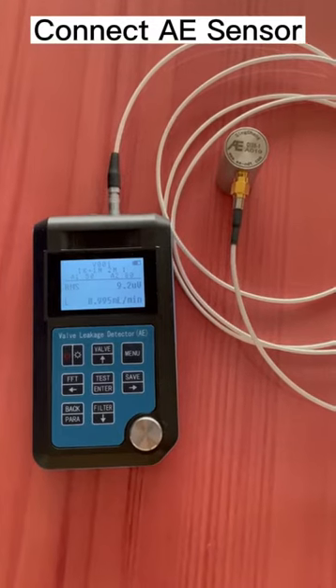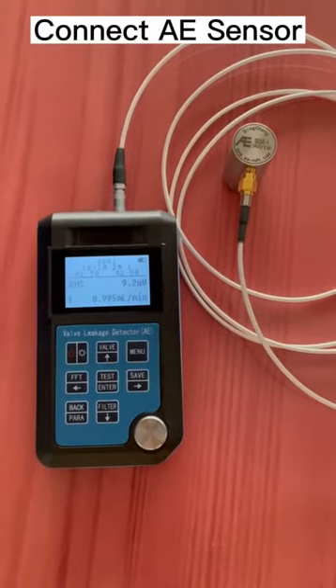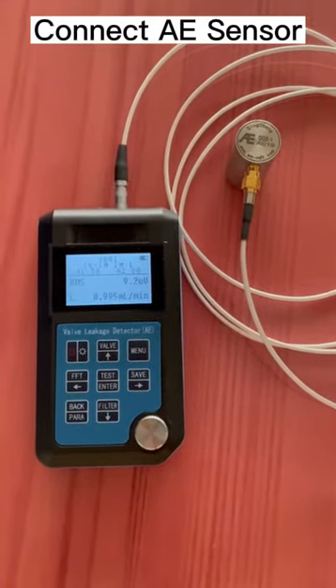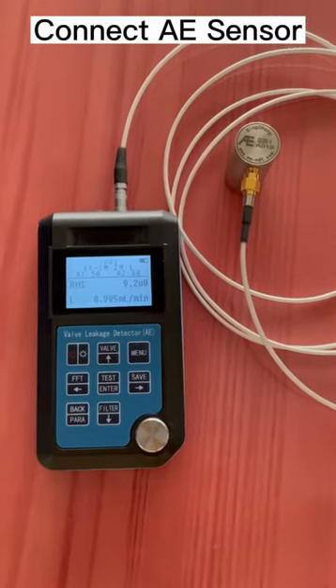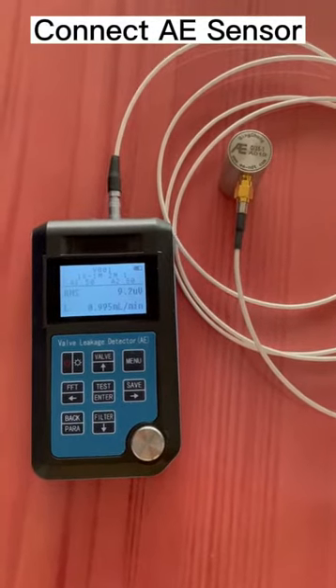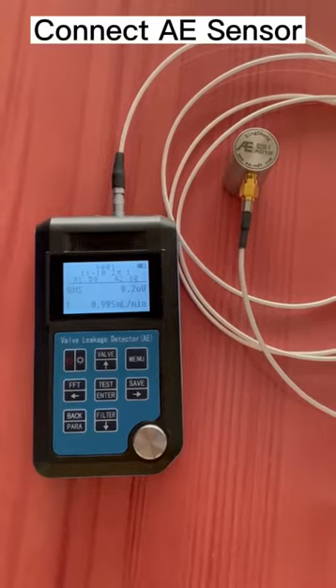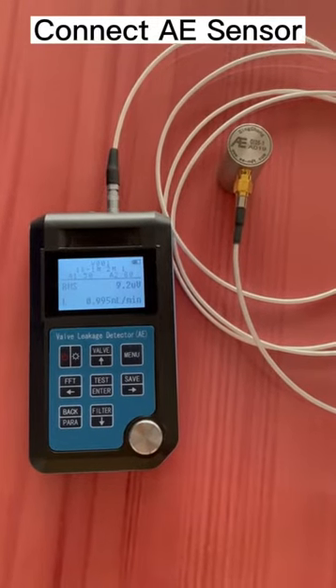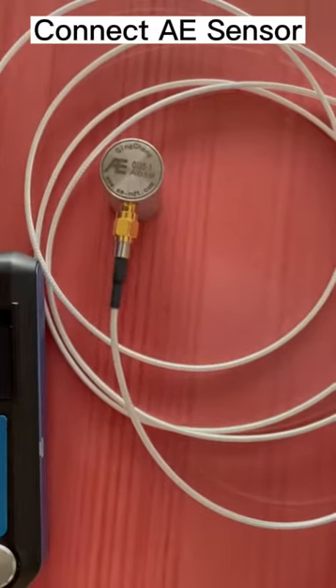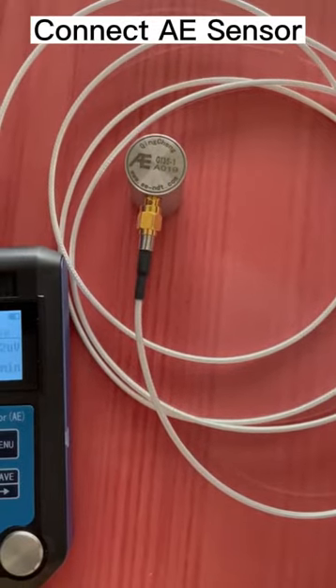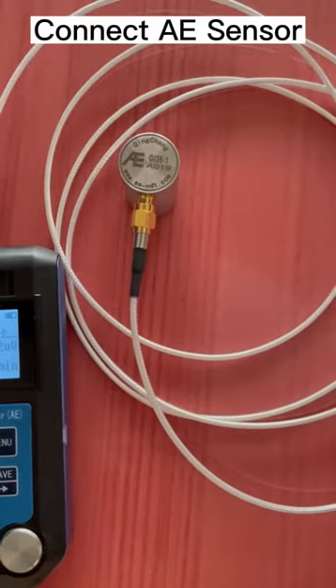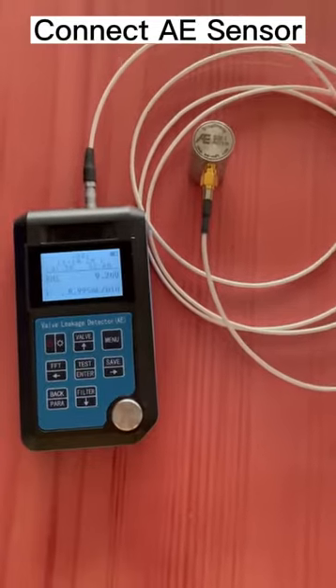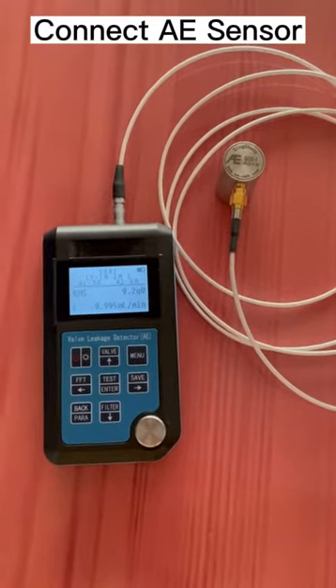The SVLD1 detector connects with acoustic emission sensors that have a built-in preamplifier. Please make sure the built-in preamp input voltage is 5 volts. We use QINGCHENG GI35/1 as the sample sensor for this demo. Connect the sensor to the SVLD1.